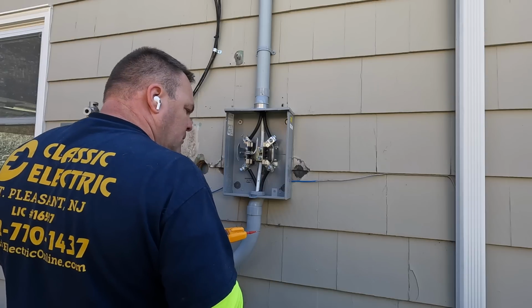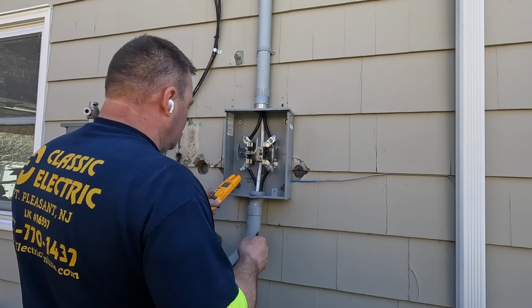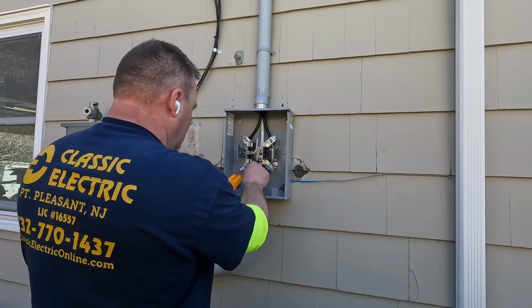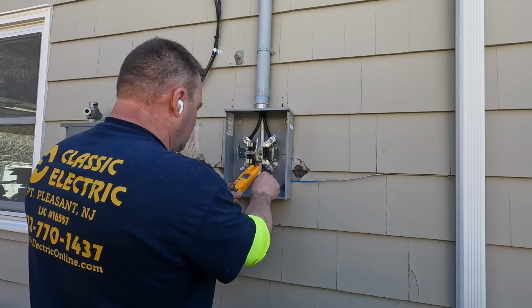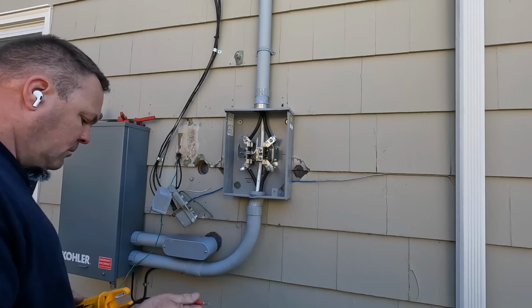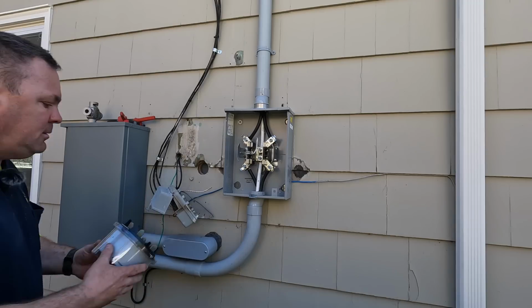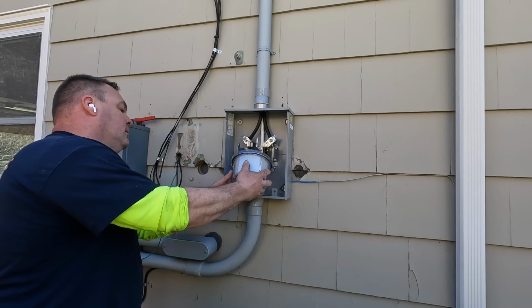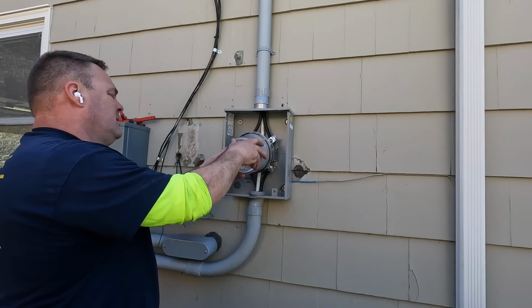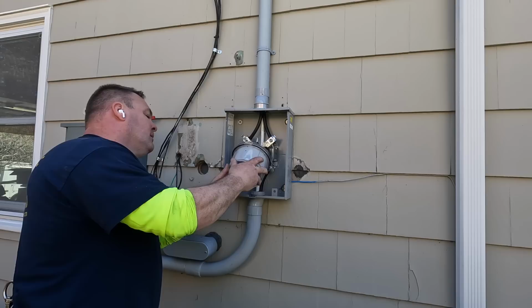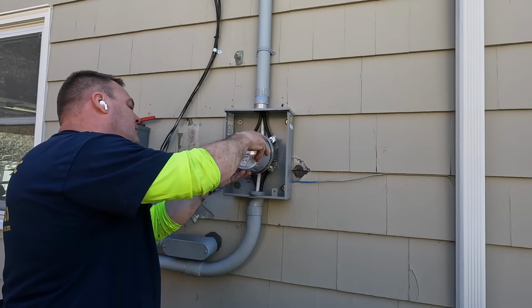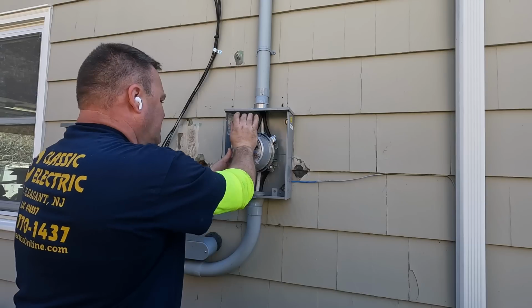All right, so here the power's back on, and I've checked it. I'm going to check leg to leg, which we call L1 to L2, and then L1 to neutral and L2 to neutral. I'm also going to check for continuity on my load connectors before I put this meter in. If you have any kind of short circuit and you go to put this meter in right here, you will get the arc flash of your life, and it's very dangerous.